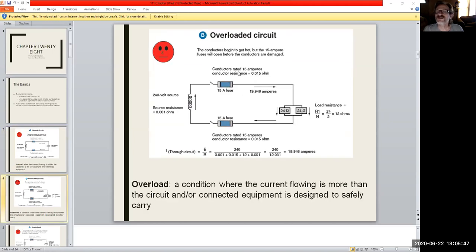Now we look at something where we have the overloaded circuit. Very similar circuit, except now our resistance has changed. In this case, let's say we experienced a short circuit that ended up throwing us 24 ohms into a parallel configuration, and what ends up happening is the resistance goes down to 12 ohms. Now, Ohm's law is very directly relational. Things remaining the same, the voltage hasn't changed at all, so it's still 240 volts. But now our overall resistance is down in the 12 ohms range, and you can see that we end up pulling nearly 20 amperes, and 20 amperes will exceed the rating of that fuse.